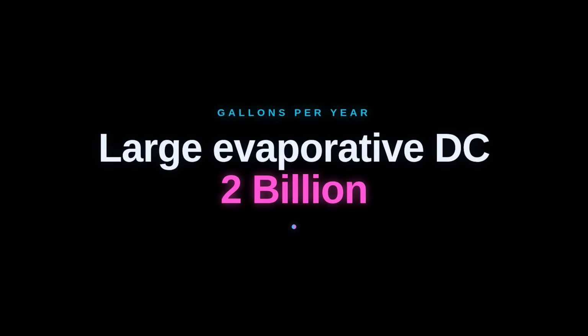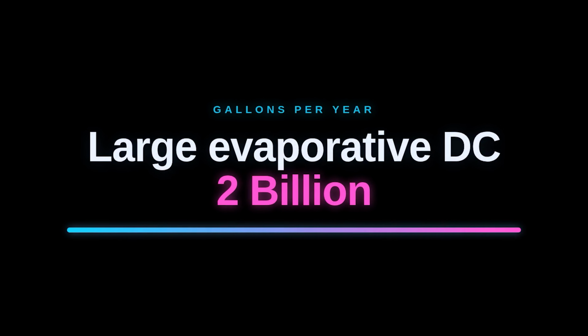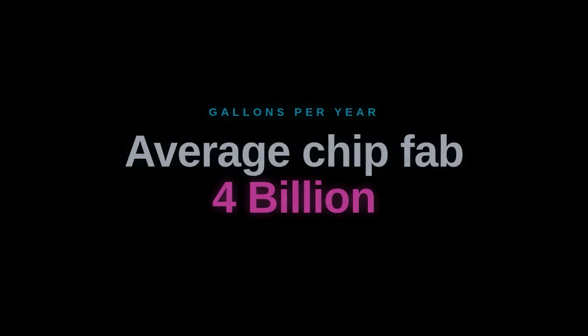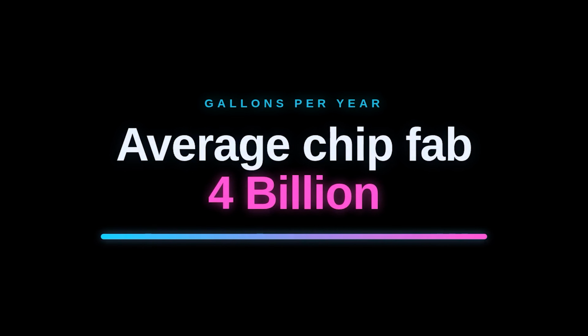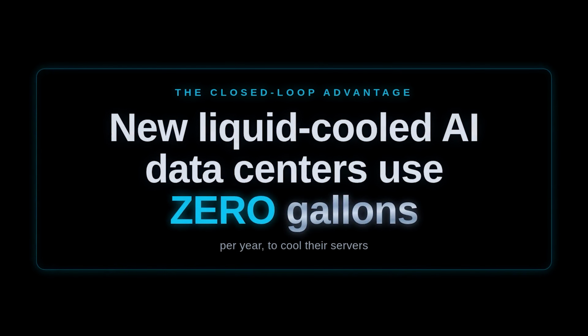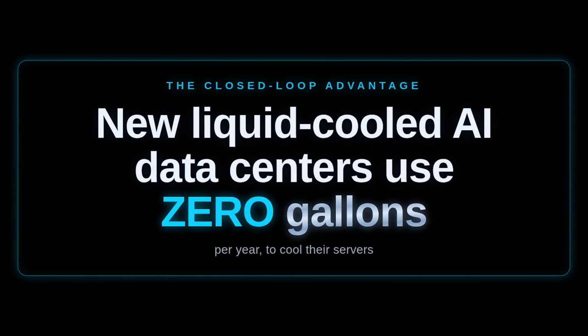But this is where it gets inefficient. A large evaporative data center will use 2 billion gallons a year of water, and an average chip fab will use close to 4 billion gallons a year. Now here's where it becomes interesting: most new AI data centers that use a closed loop liquid cooling solution will use 0 gallons a year when it comes to cooling their servers.